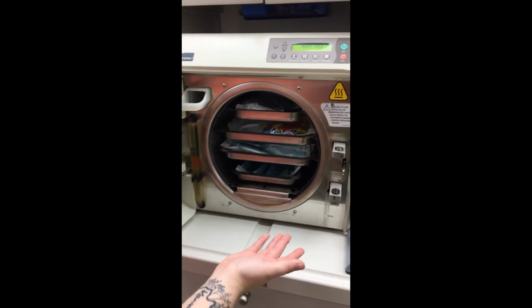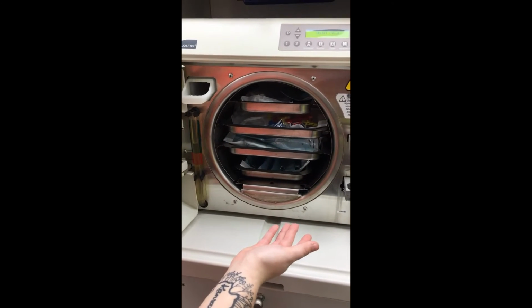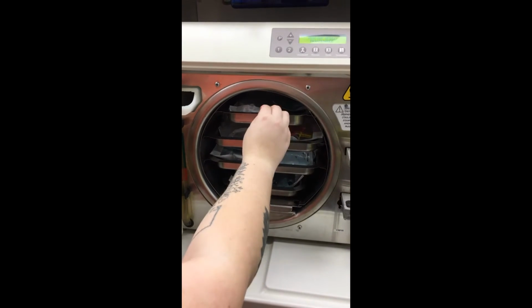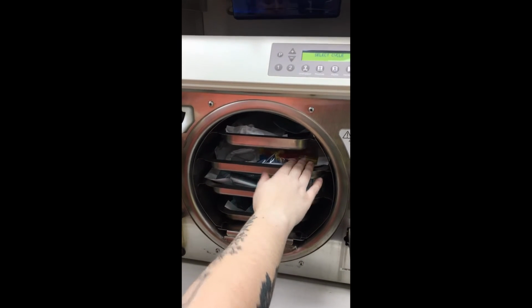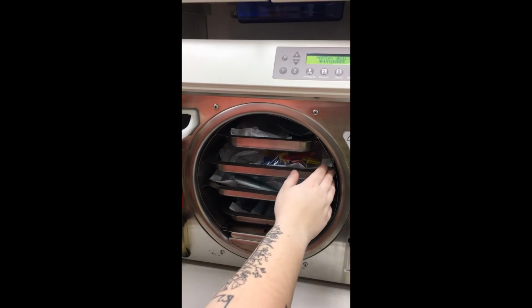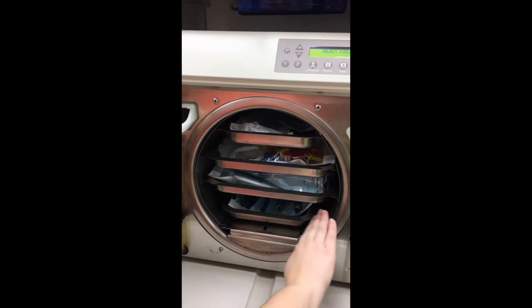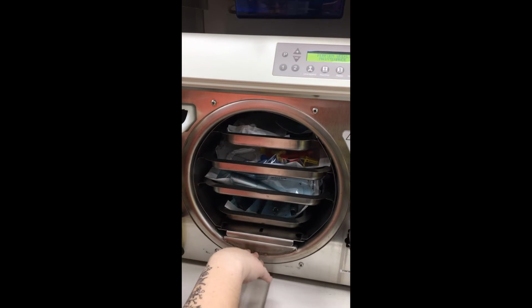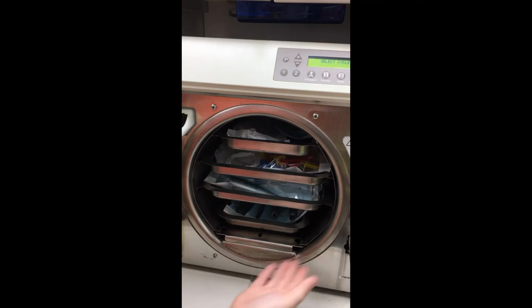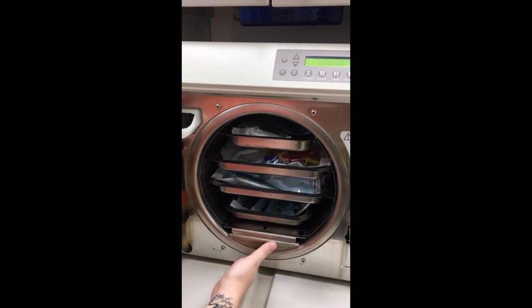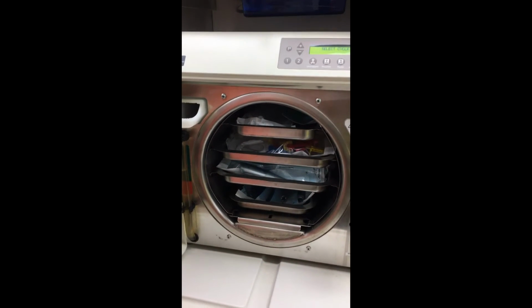When you're loading the autoclave, you'll want to make sure that the packaging is paper side down. You don't want any of it to touch the chamber walls. You want to make sure bigger items are on the bottom and plastic has to go on the top, otherwise the heating elements in the autoclave will melt them.